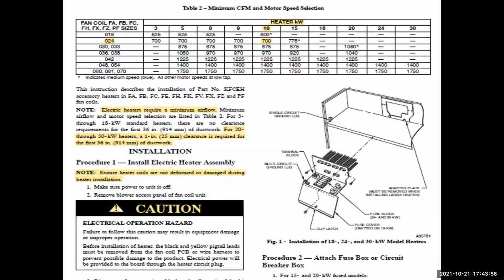Okay, the electric heaters require a minimum airflow. Note, fan coil units with or without electric heat require a minimum airflow. So we're going to go look at a 2-ton fan coil unit, and we're going to pick 10 kW. They're letting you know that you're going to need 700 CFM. So you will go to your fan coil unit. You will check what your static pressure is going to be and make sure it can deliver the minimum CFM. So a little bit more is better than being right at the number. That way, if they close some ducts up, if they use a different style of filter or the filter gets plugged, we still have some wiggle room.